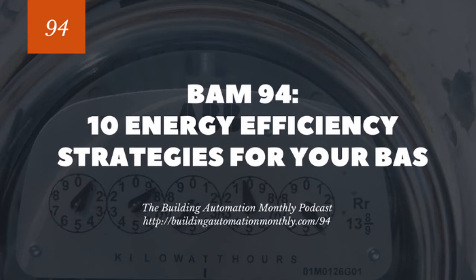You have to take into account the humidity level of the air outside. You have to take into account the exposure of the building. Is it a primarily southern facing building where it's going to take advantage of solar gain? You have to factor all of these things in when you're creating your changeover temperatures. If you simply stick with the tried and true 60 or 65 degrees for your cooling and 50 or 55 degrees for your heating, you may be conditioning a building and kicking on heating or cooling when you don't need to.